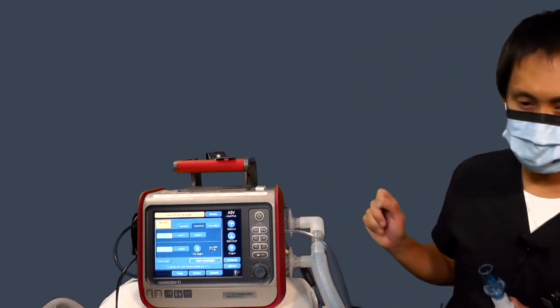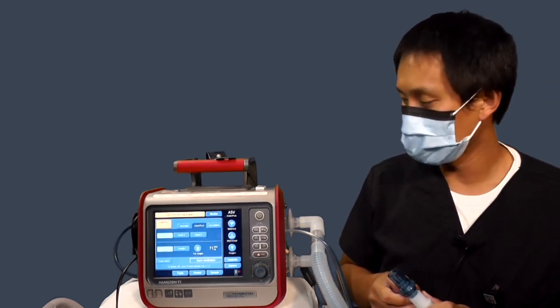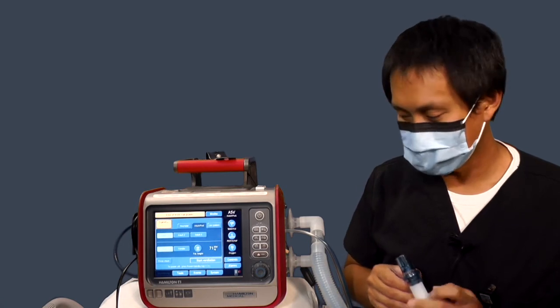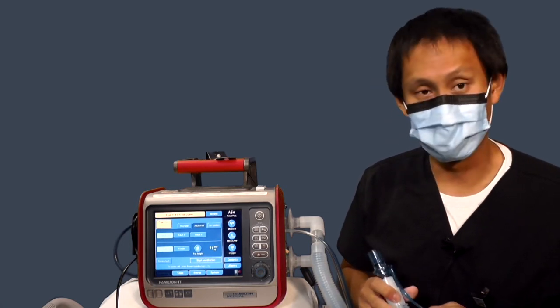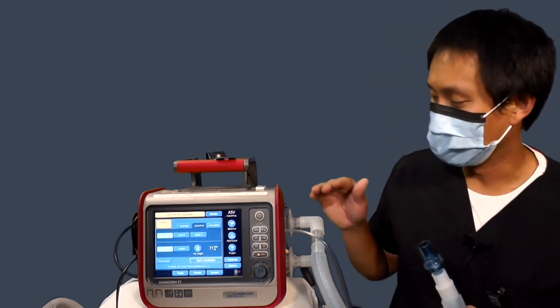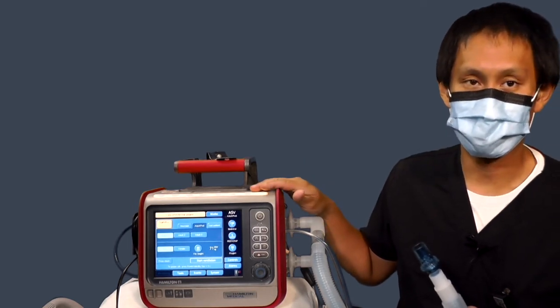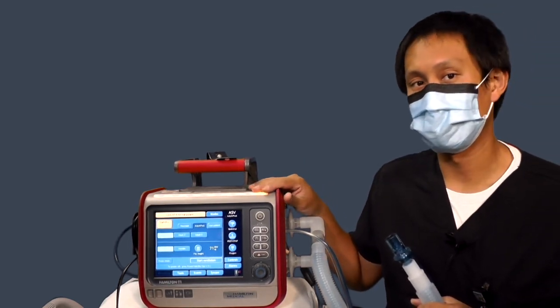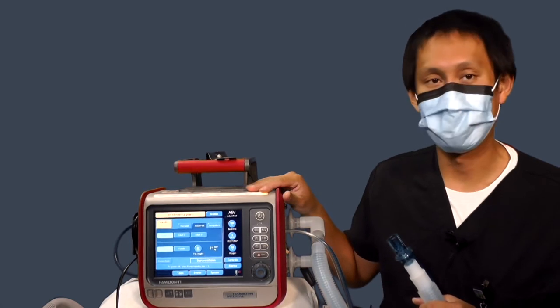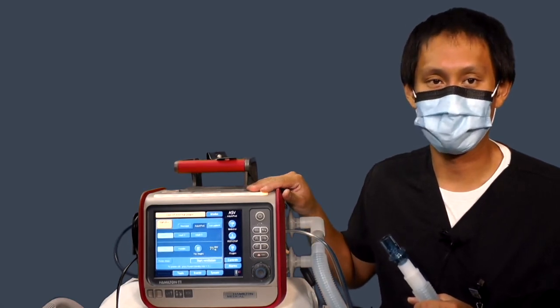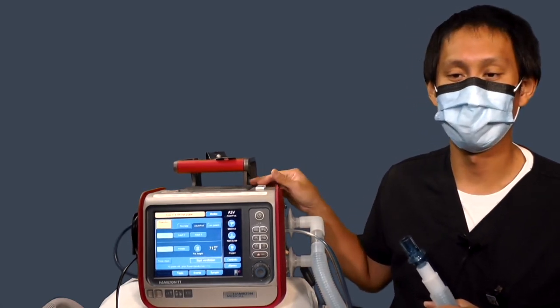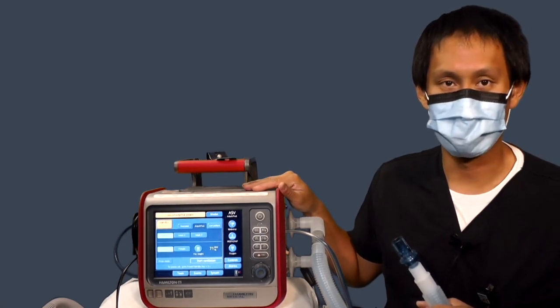Those are the two pre-use calibration checks you have to do prior to placing it on a patient. They're fairly short and do not take a lot of time. And the other thing when you're doing your pre-use check is it does not require you to connect the ventilator to any gas source. It actually entrains room air when it's doing this calibration.